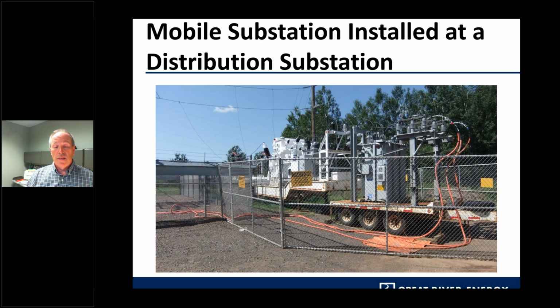One of the things in talking about security and safety, once the mobile sub is energized, we have previously installed, before it's energized, an equipotential mat. This is for operator safety, so when he comes into the mobile sub, he stands on that mat before touching anything on the mobile, because we have our controls cabinet on the mobile, and we want to make sure he becomes at the same potential of the mobile in case there happens to be a fault.